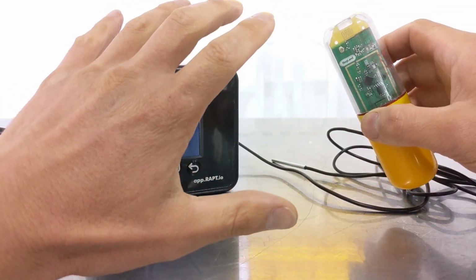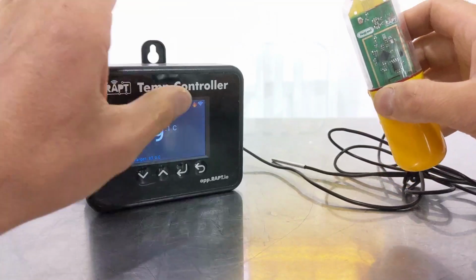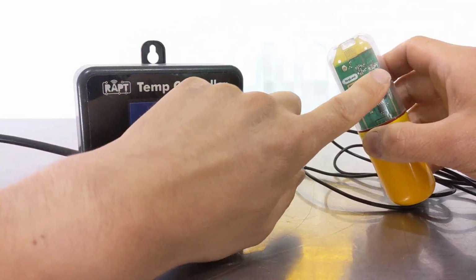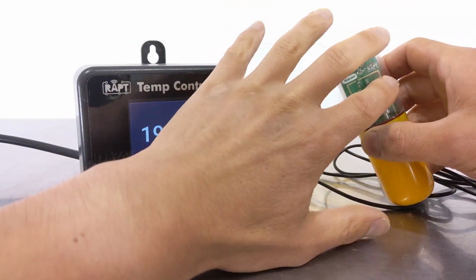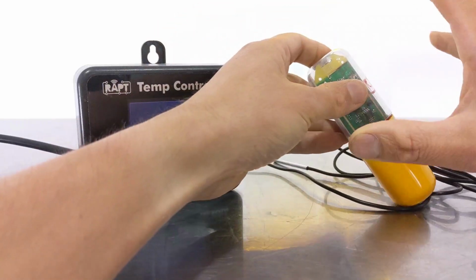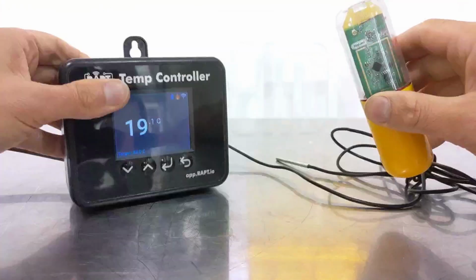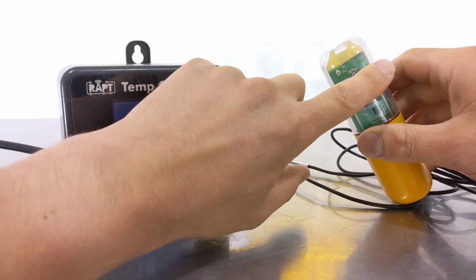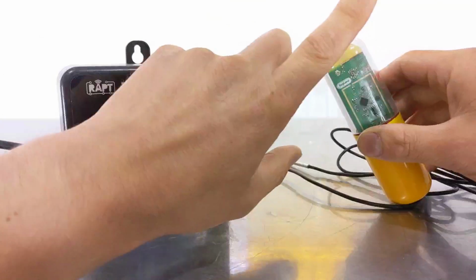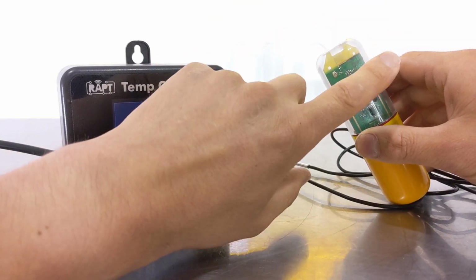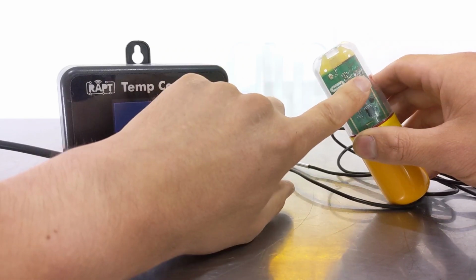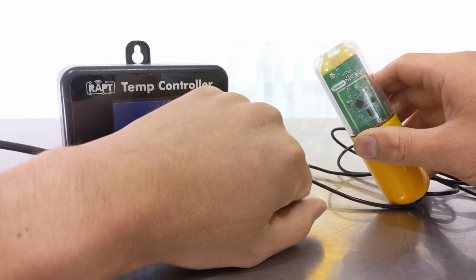And the reason why we don't do calibration on the controller for the pill is because the pill needs to give out a calibrated temperature reading. So when it's giving out that Bluetooth beacon, which this device is picking up on, the Bluetooth beacon has to be calibrated, which means you have to go into the firmware of this device. So you connect to the pill with your phone and then basically put in the calibration figure.